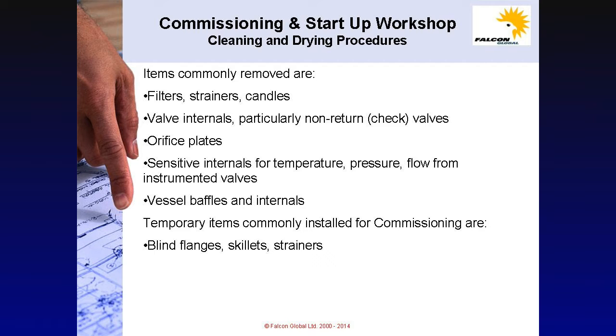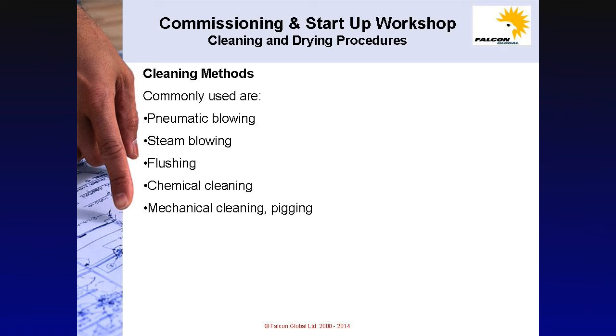Items that are commonly removed are filters, strainers and candles. Also valve internals, particularly non-return valves or check valves, orifice plates and sensitive internals from temperature, pressure and instrumented flow valves. Vessel baffles and temporary internals are also often removed. Items temporarily installed for commissioning are blind flanges, skillets and strainers. Again, these need to be shown on relevant drawings.